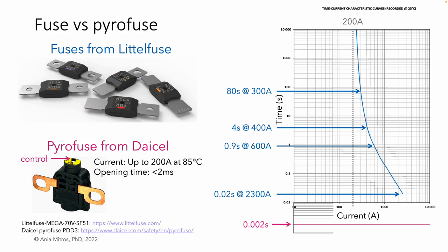Given that the control is electronic, we can design the controls to activate the pyrofuse at any current of our choosing. For example, we can choose to activate the pyrofuse at some current just above our 200 amp application maximum. We would analyze system noise and sensor error to select the margin between our maximum application current and our pyrofuse activation current, aiming to ensure that we never fire below 200 amps. A pyrofuse allows a smaller margin between our maximum normal operation current and the range of fault currents that trigger our safety device than what's possible with a traditional fuse.